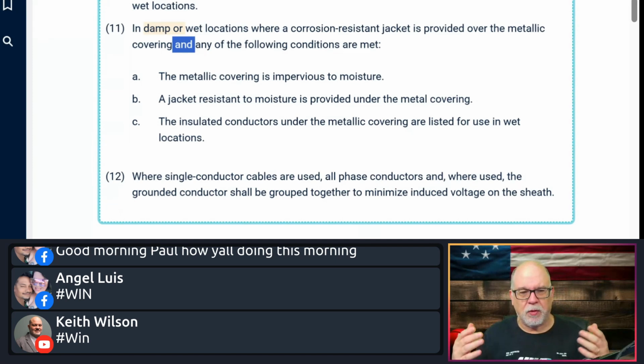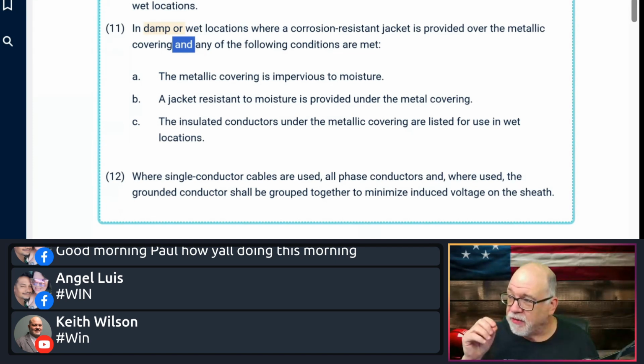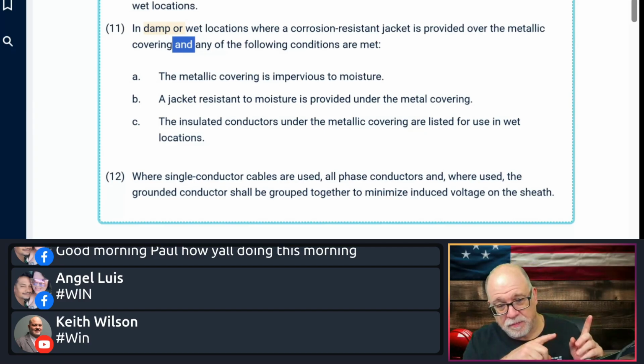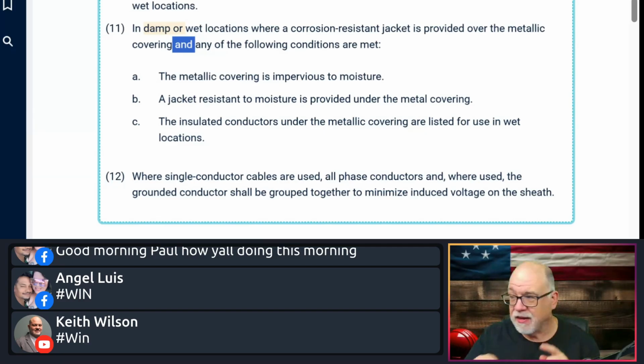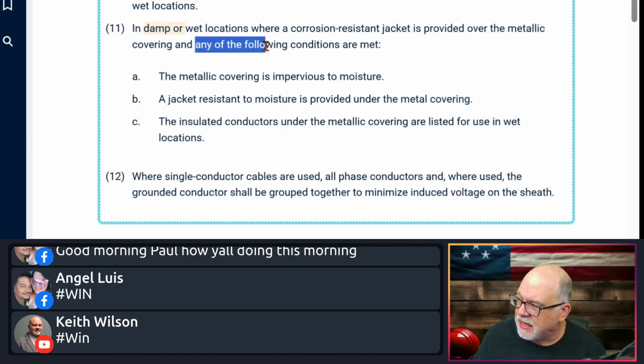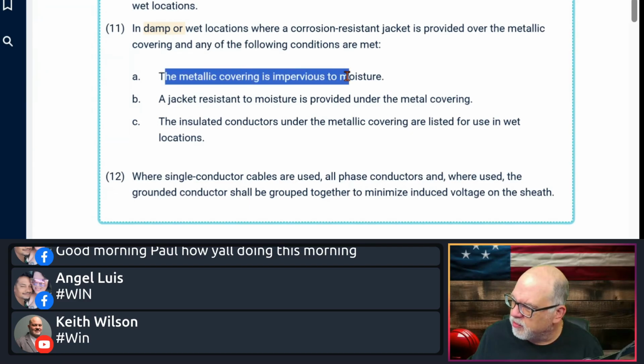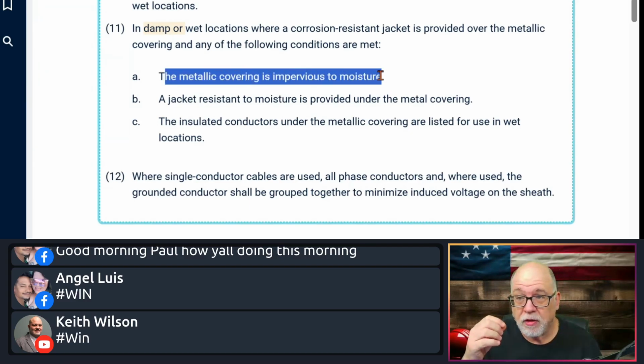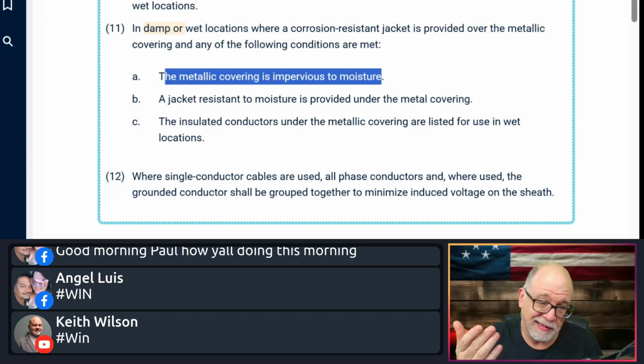And notice the "and" here, and this is an important part to always talk about to people, the power of the word "and." If it had said "or any of the following," then you would just run down the list and say, I'll pick whichever one I want. It says "and." So it has to have a protective coating on these types of MCs, and it has to have any of the following. Now, the first one says a metallic covering that is impervious to moisture. Well, the smooth type of MC would be impervious to moisture. It's an extrusion process, so it would be fine.